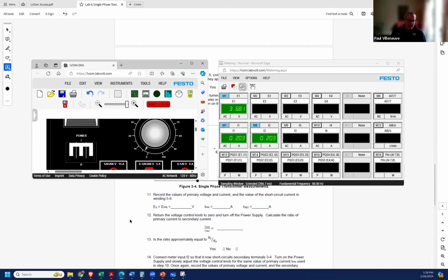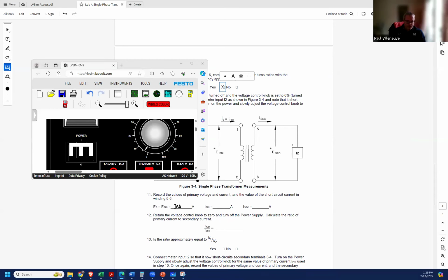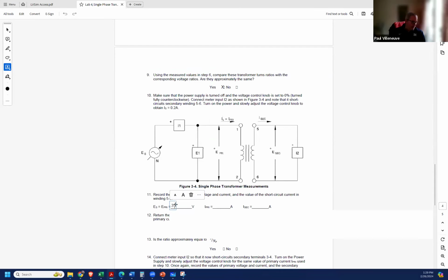And that's perfectly okay. And if you remember from the short circuit test, I'm going to get a voltage source that I'm going to adjust so that I get rated current flowing into the transformer. Well, look how low that voltage is. That winding was rated for 120, but I'm only at 3.7 volts. So now I can go ahead and enter in my primary voltage, which is 3.684. My primary current is 203 milliamps.